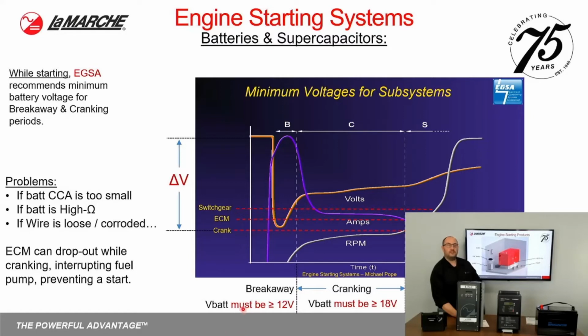The EGSA only has recommendations against the cranking requirement, but your engine ECM, or even the switchgear that might be operated by a larger generator, could be affected by this momentary dip of voltage. That's why it's very important to size the system properly and also maintain your system. If the cold cranking amp rating of the battery is too small, you'll have too large a voltage dip and could encounter a problem. If the battery internal resistance is high because it's aged or hasn't been taken care of, you'll have excessive voltage drop and may start to compromise these components. Same if the wire is loose or corroded. Either way, you could run into a scenario.